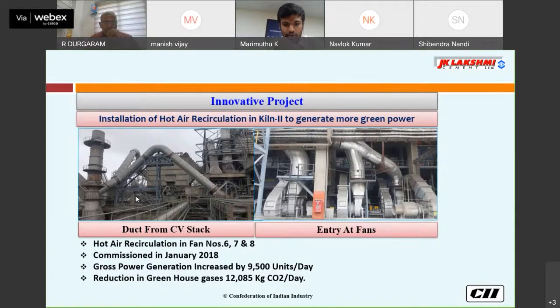This is one of the case studies from JK Lakshmi Cement. On the left side figure, we can see the recirculation duct from the stack, which is given to the middle fan of the clinker cooler. On the right side, the new fans are there. Hot air recirculation is given to fan numbers 6, 7, 8 out of 10, and it was commissioned in January 2018. It has increased the output and given savings of around 9,500 units per day. It also helped reduce 12,000 kg of CO2 per day.